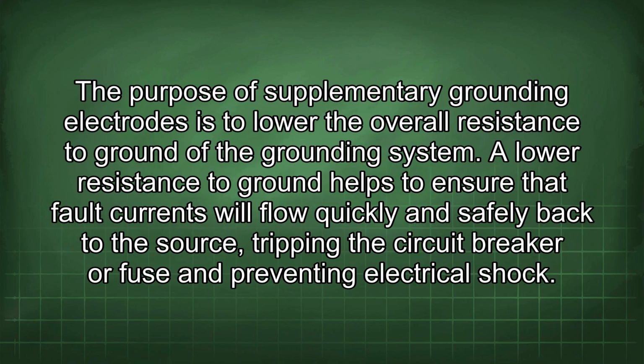The purpose of supplementary grounding electrodes is to lower the overall resistance to ground of the grounding system. A lower resistance to ground helps to ensure that fault currents will flow quickly and safely back to the source, tripping the circuit breaker or fuse and preventing electrical shock.